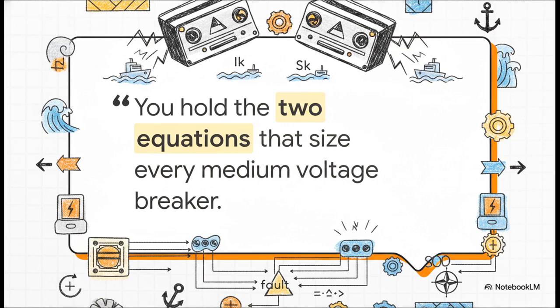So you now hold the two equations that size every medium voltage breaker on a marine switchboard. This right here is your sizing toolkit. Just by understanding this, you get exactly why engineers are so obsessive about fault calculations. You know for a fact that fault contribution is fiercely cumulative across every connected source, not just the ones running at max capacity when the fault hits. You have the mathematical foundation of survival.